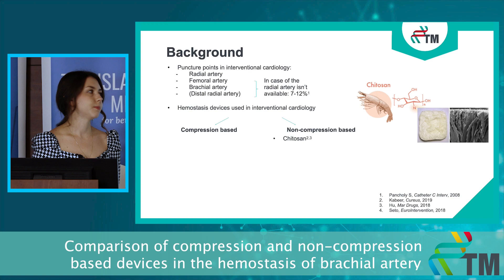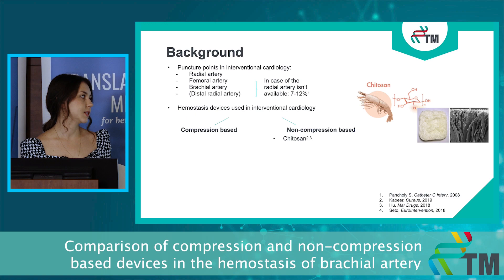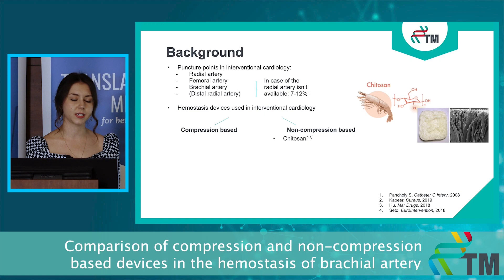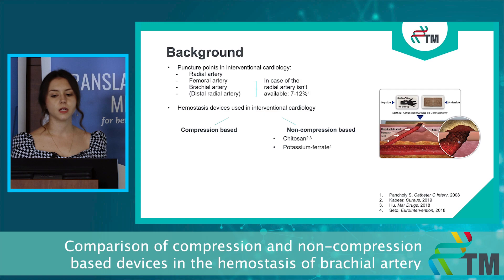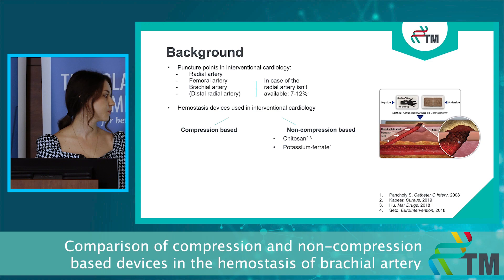I would like to highlight two of the non-compression based devices used in our department. The first is the chitosan-based one — chitosan is made from shells of shrimp, and its mechanism of action is based on the electrical polarity difference between the positively charged seal and the negatively charged blood, forming a strong mechanical barrier. The second is the potassium ferrate based device, a highly reactive substance which, when encountering water and blood, decomposes into ferric oxide, and the released cationic iron activates the thrombocytes to initialize the coagulation cascade.